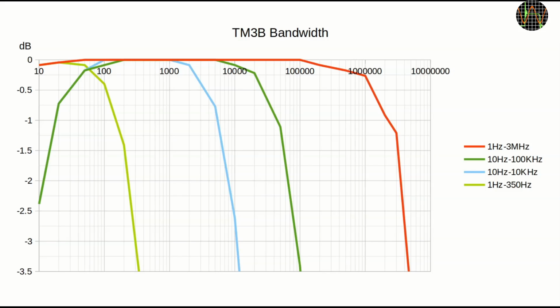Now, being calibrated, I did measure the bandwidth taking into account the 4 possible settings of the bandpass switch. It is notable that the upper limits listed on the bandpass switch correspond pretty much accurately to the 3 dB points. In other words, measuring for example something with a switch set to the 10 Hz to 10 kHz position, which is the light blue line in this graph, does not mean frequencies of up to 10 kHz can be measured. Far from it. If one really wants to know accurate voltages, the useful frequencies are limited to between 100 and 1 kHz.